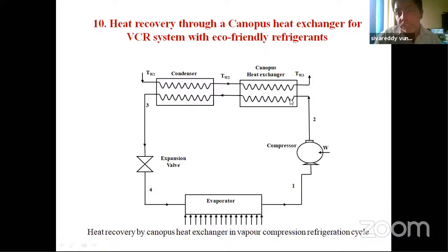But this 30 degree temperature difference can be utilized for at least crate washing. Suppose in a dairy industry, crate washing requires only 50 degrees. You can extract that 45 to 70 degree sensible heat and use it for crate washing, or for textile industry cloth cleaning, or near hostels for cooking or bathing purposes. But for small capacity, cost effectiveness doesn't come. For large capacity, we can achieve very good cost effectiveness, I think.